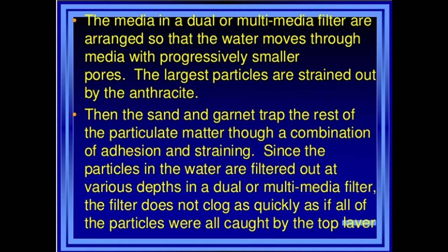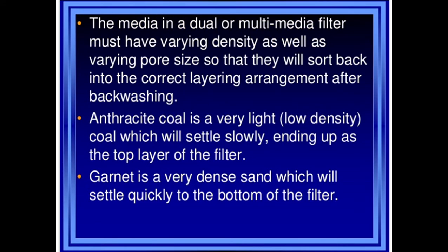The largest particles are strained out by the anthracite, then the sand and garnet trap the rest of the particulate matter through a combination of adhesion and straining. Since the particles in the water are filtered out at various depths, the filter does not clog as quickly as when all particles are caught by the top layers. The multimedia must have varying density as well as varying pore size so that the media will sort back into the correct layering arrangement after backwashing.